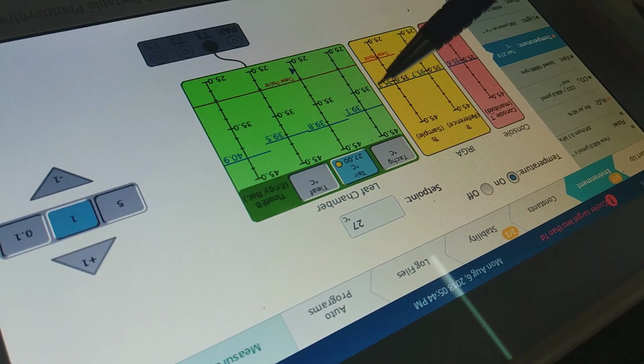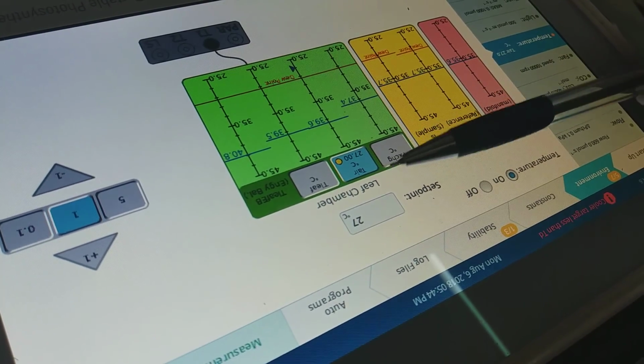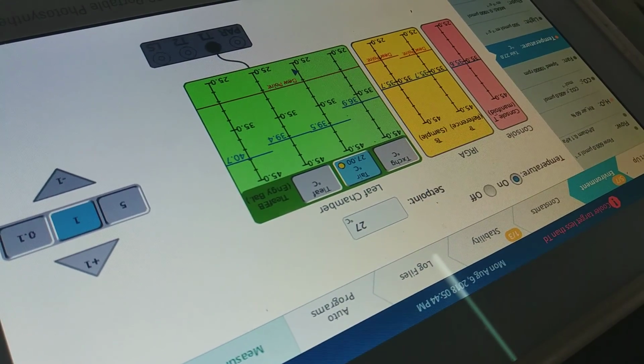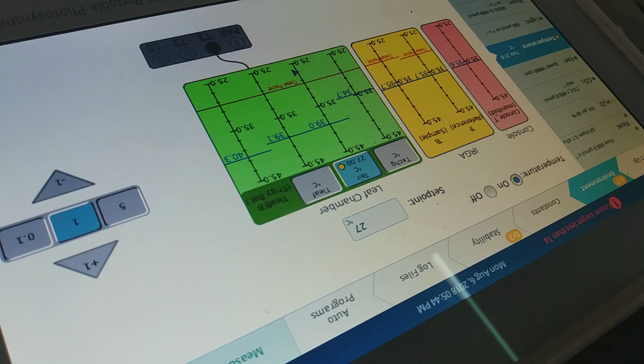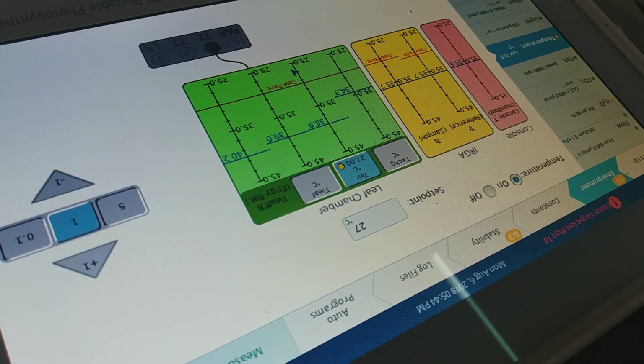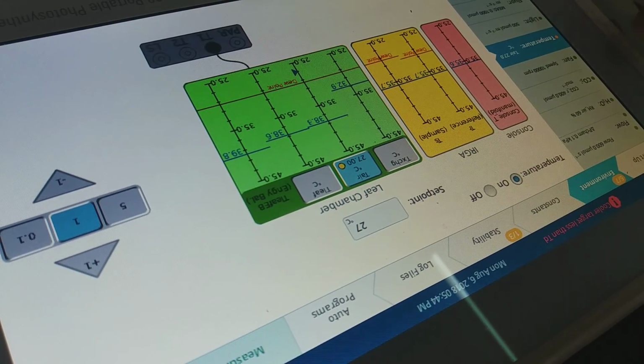It's like this. There are three things that you can control. When you decide to control one thing, it will override the other two. It's the same for other sections. Earlier you had vapor pressure deficit, saturation deficit, and RH of air. If you choose to set RH, it will override vapor pressure deficit and the saturation deficit. If you choose to set vapor pressure deficit, it will override the RH. Like the fan speed earlier.